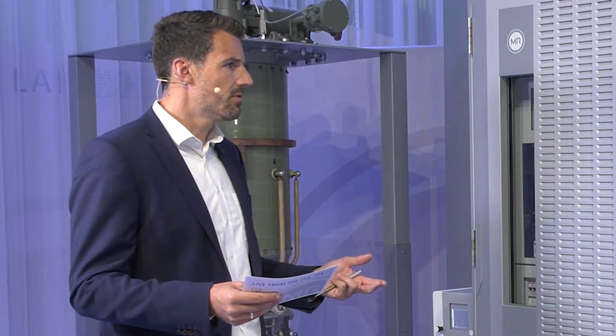The second big function package is monitoring, specifically DGA monitoring, gas monitoring, temperature monitoring. We can realize with the system bushing monitoring, of course, and last but not least, tap changer monitoring realized by motor current index or vibroacoustical monitoring.